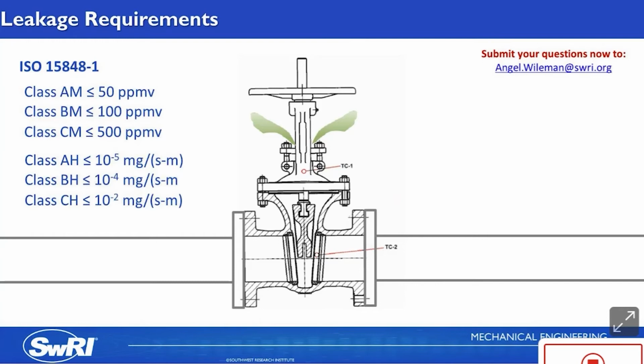Now, the ISO test standards have different requirements for stem leakage compared to body leakage. For ISO 15848-1, the allowable stem seal leakage is broken up into different tightness classes. A is the most restrictive and C is the least restrictive. The allowable leakage for methane testing ranges from 50 parts per million by volume to 500 parts per million by volume. But for testing with helium, the allowable stem seal leakage is defined as a measured flow rate, not a concentration. The unit is defined as mass flow rate per stem perimeter length. Therefore, the allowable leakage will increase for valves with larger stem diameters.